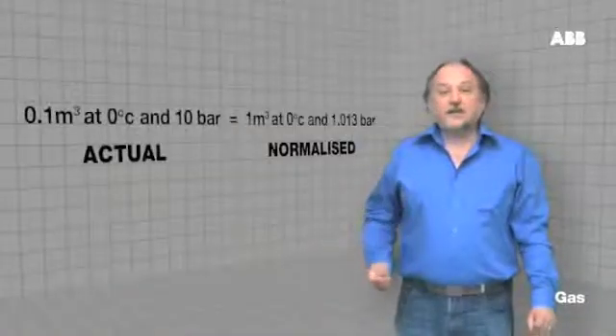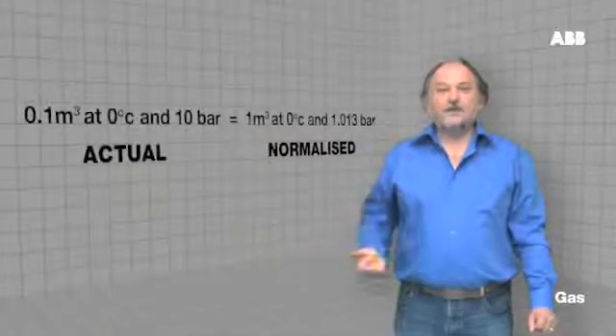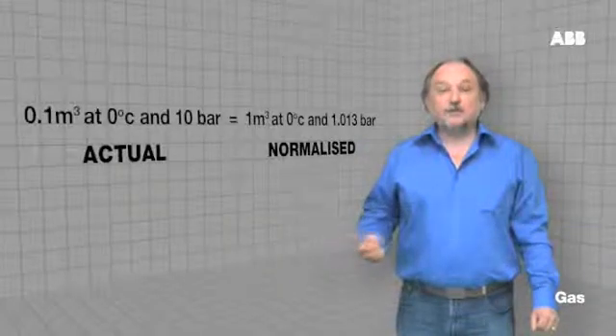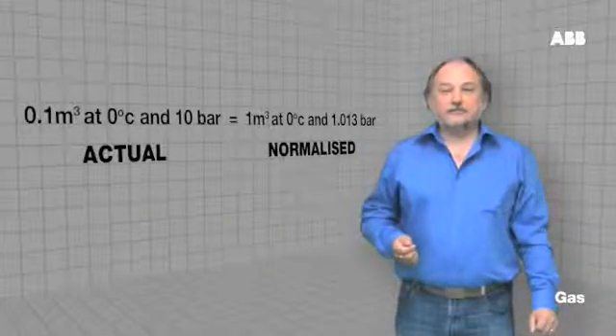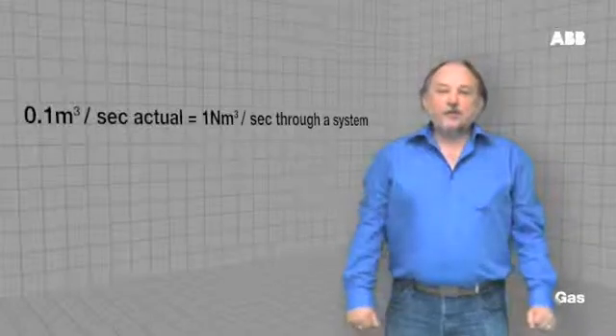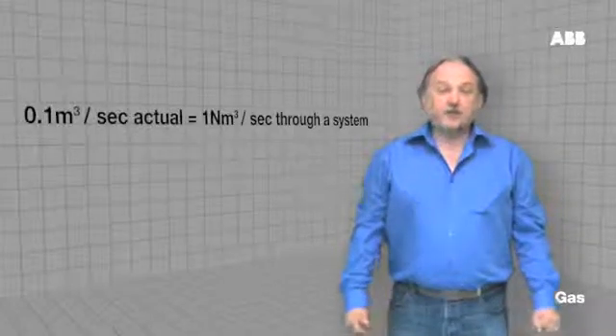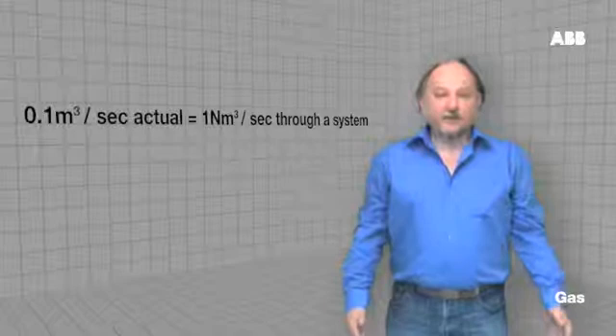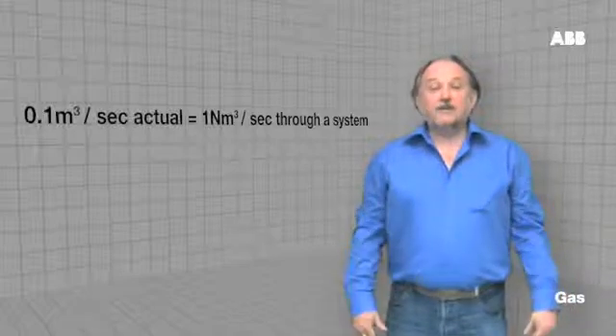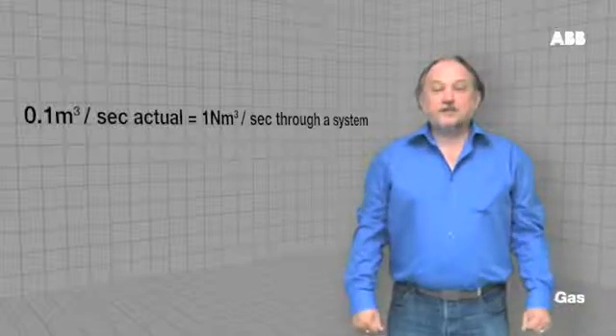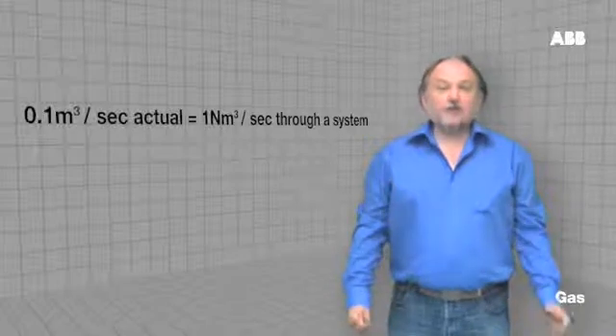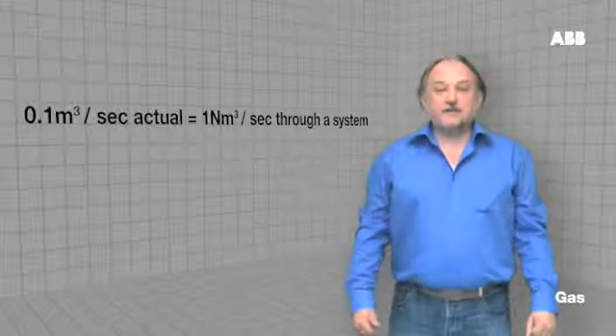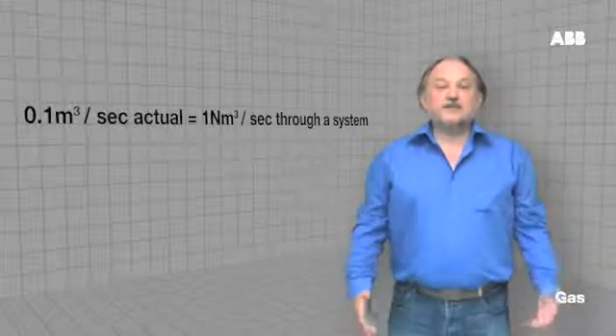Here we have an example of a comparison between normalised volume and actual volume. If we run both of these volumes through a system, 0.1 cubic metres actual per second is actually equal to one normal cubic metre per second. The volume flow is different in both cases. However, the mass flow rate is identical.